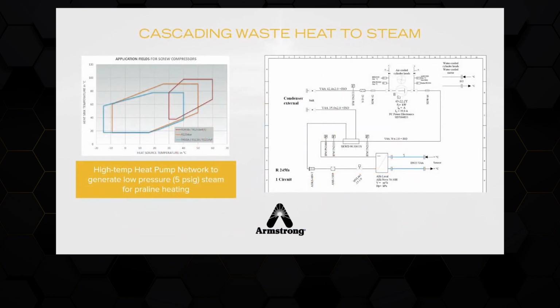If you are closely following me, you might have realized that by now, most of the steam that's used at Skywalker is used at a temperature which is less than 200 degrees Fahrenheit, except for one process which is praline preparation, where steam is used at 5 psig for heating kettles. Now, even by optimizing steam and condensate loops and by implementing best-in-class maintenance programs for steam traps and insulation, the overall efficiency of the steam and condensate system at the Skywalker plant could only reach 80%. So we started to work on alternate ways of meeting this demand.